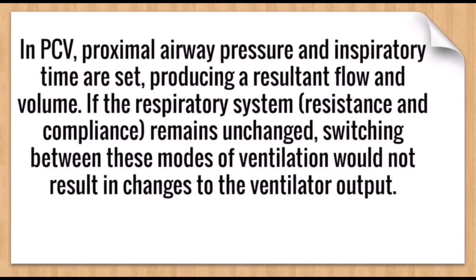Now in pressure control ventilation, proximal airway pressure and inspiratory time are set, and that will result in flow and volume. So depending upon the proximal airway pressure and inspiratory time we have set, it will determine how much flow is to be delivered and what the tidal volume should be.